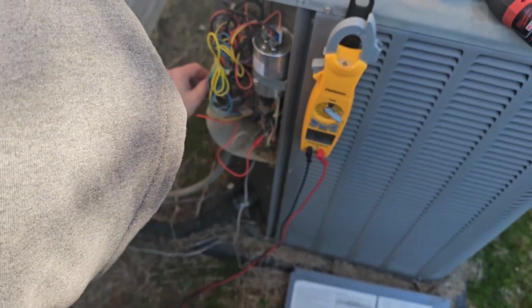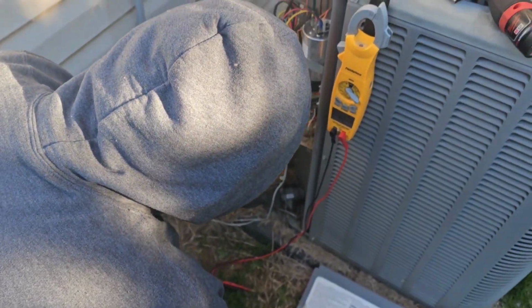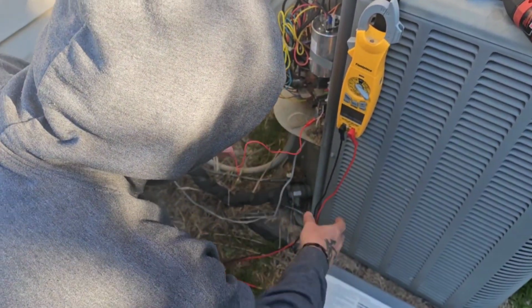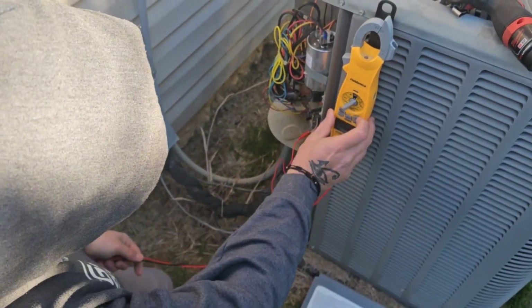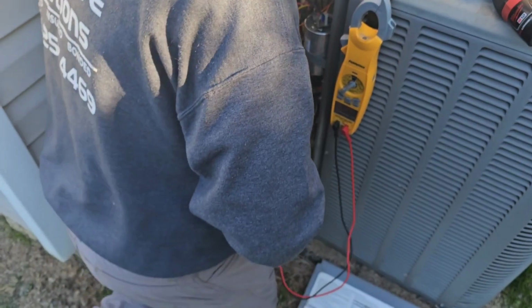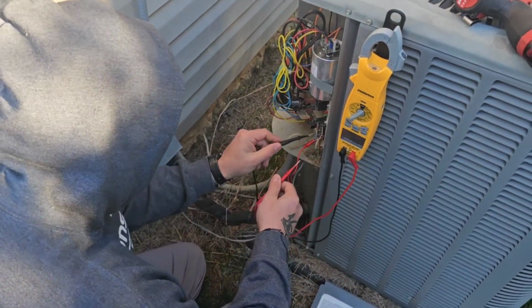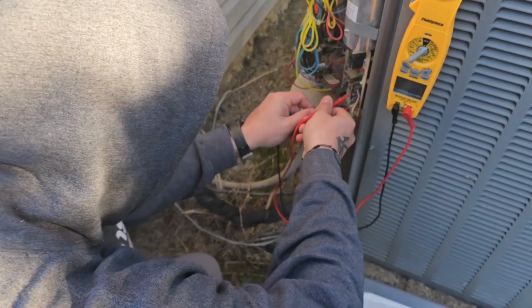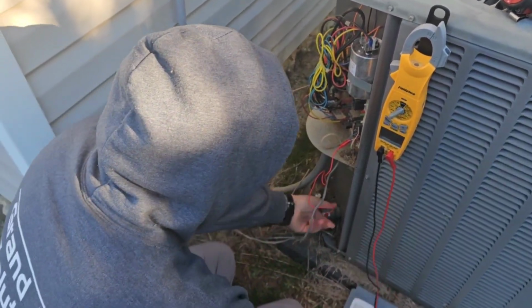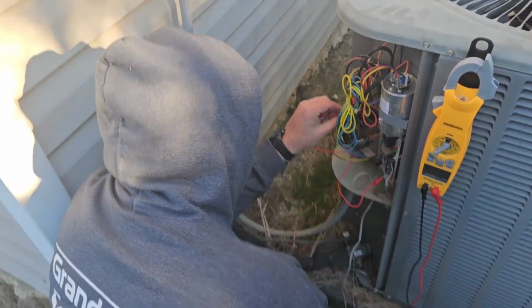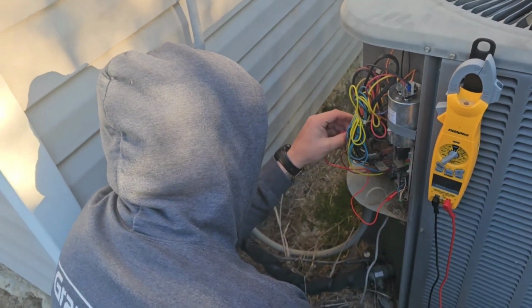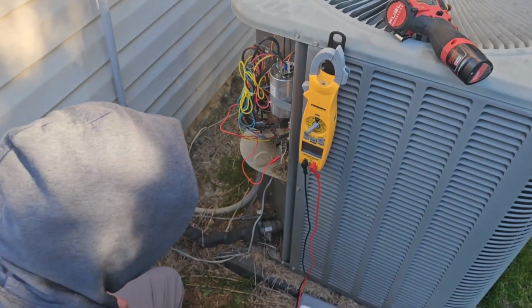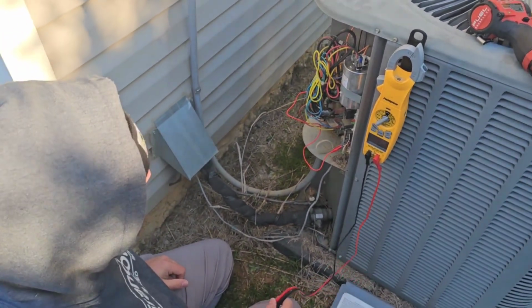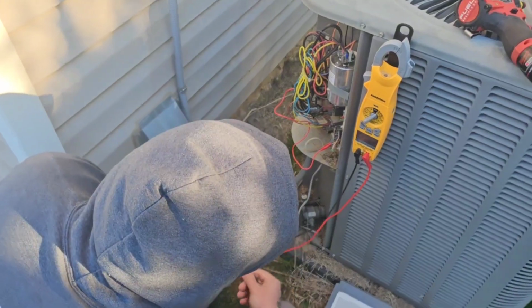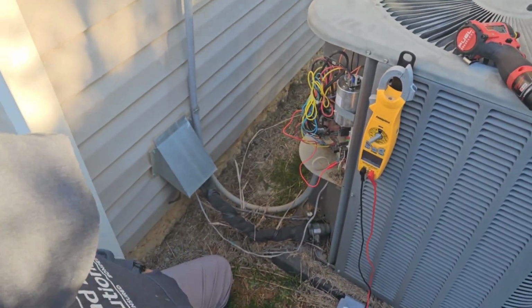When the call is there, it should be fine. It should click in. Double check right now on your meter with voltage that there's still not a 24 volt call yet to the thing. Just check Y to see real quick. Okay, so yeah, it's still on a delay. So yeah, you can put your meter there on that tab and just leave it there. The tab on the side of the coil, the contactor that you just put it on. You just did good. We gotta wait now.